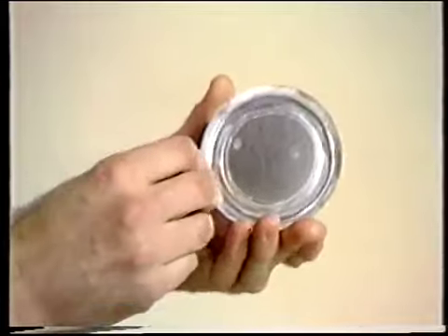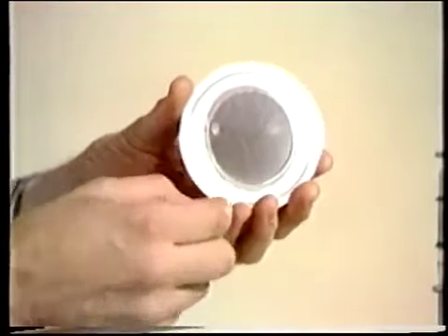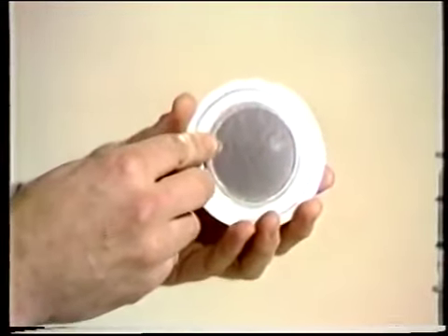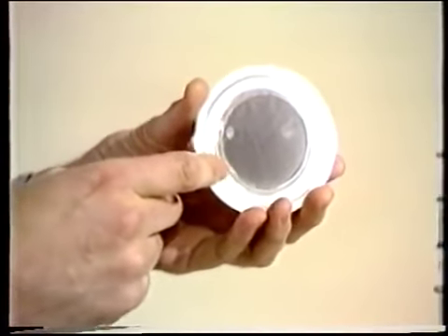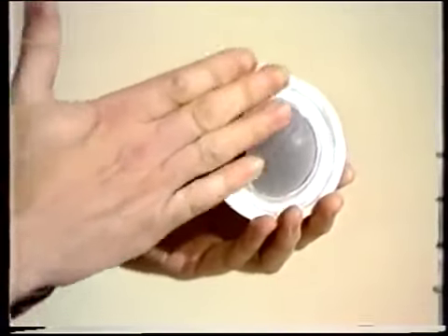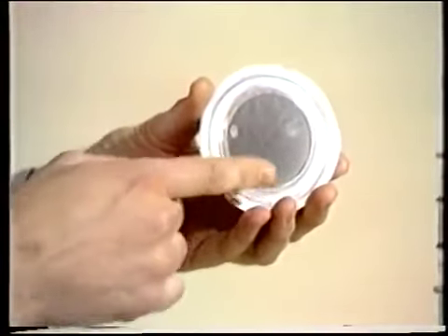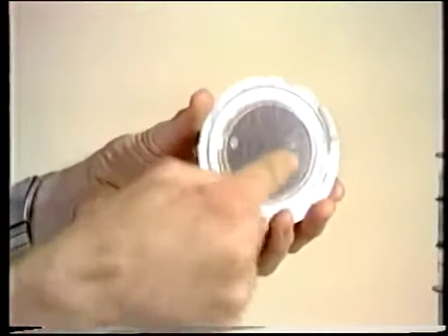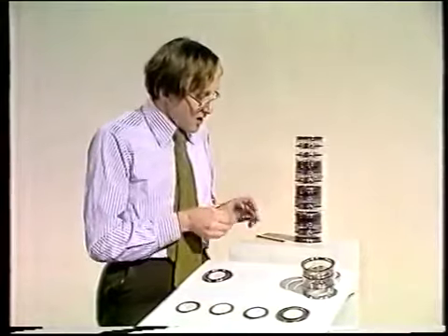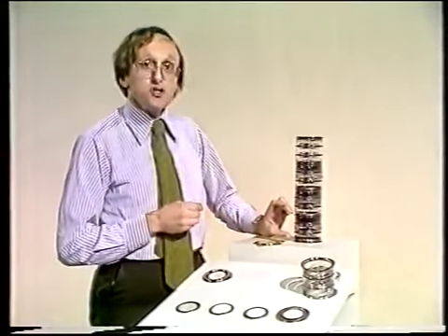We don't see the white at all. What we see is a sort of black surface, but through the black we see some spots of aluminium. In fact, the whole of the phosphor is coated with a layer of aluminium. That allows the high voltage to be applied across the plane of the phosphor. And the black layer there is to stop any of the output photons from finding their way back into the input. Well, as I said, it's a 4-stage tube.